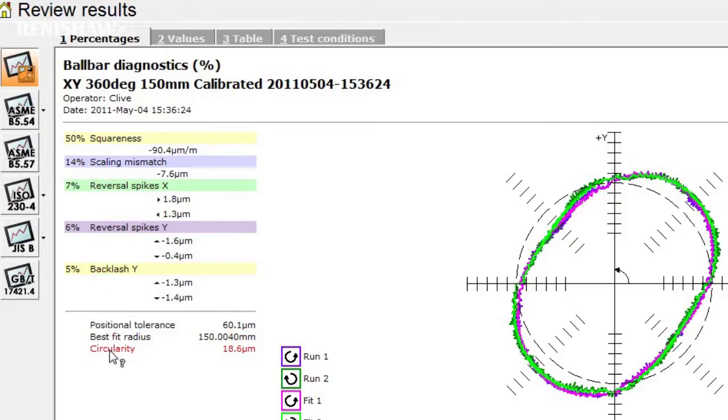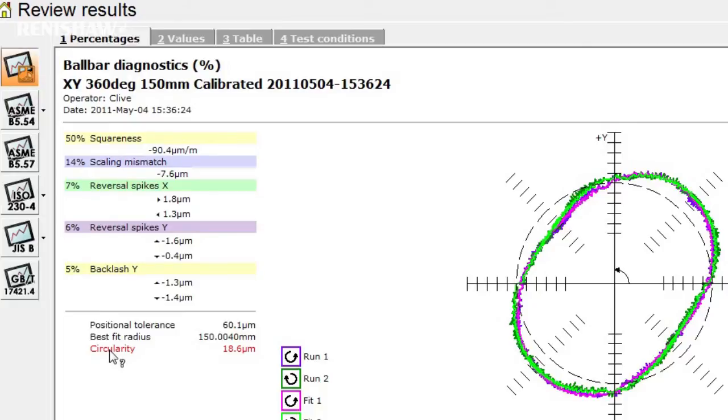The circularity value is defined as the difference between the largest and smallest radius measured by the ball bar, and as such includes the effects of all the errors in the machine. It is therefore the key value that is used to compare and grade machines.